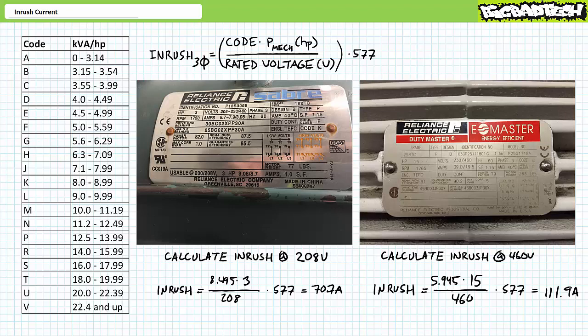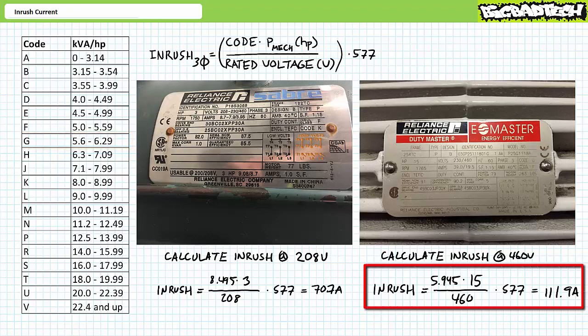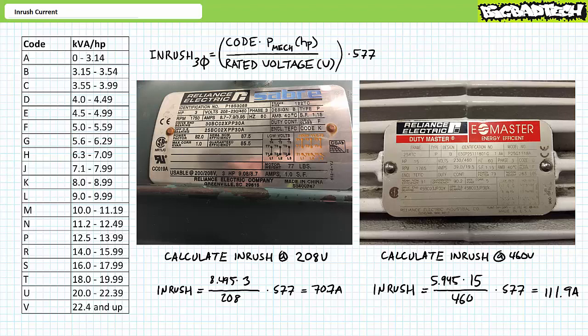The second example features a 15-horsepower motor intended to operate using 460-volt three-phase AC in the high-voltage configuration with a locked rotor code of G, meaning it has a kilovolt ampere per horsepower constant with a low of 5.6 up to a high of around 6.3. Center of mass is around 5.95. Substituting into the inrush equation results in an estimate of roughly 112 amps. As large as this value is, it is only roughly 5.7 times the rated current of 19.5 amps — illustrating that motors can exhibit wide ranges of inrush in relation to rated current, sometimes more than six times, sometimes less.